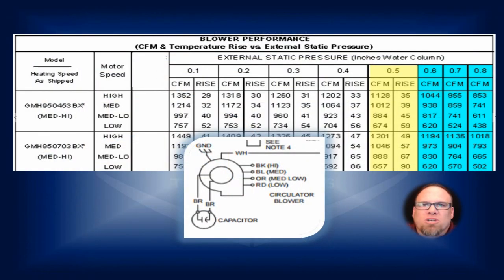So here's a more expanded blower performance chart as far as your static pressure chart. If you look over to the left, the left shows you the model of the equipment, and you have to make sure that you're looking at the right model. Okay, for instance, the one that's up the top there, the GMH95-0453BX. It's telling you that you've got your fan speeds set at medium and high. Okay, so your medium is going to be your furnace speed on high, and then your high speed is going to be your air conditioning speed.